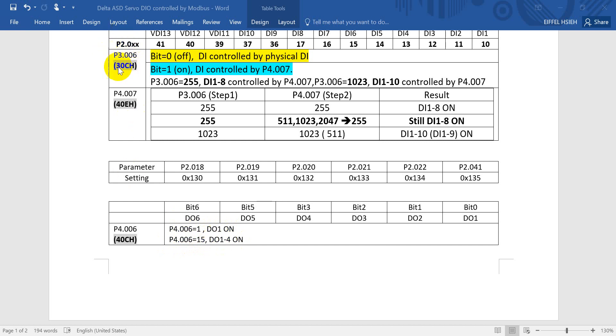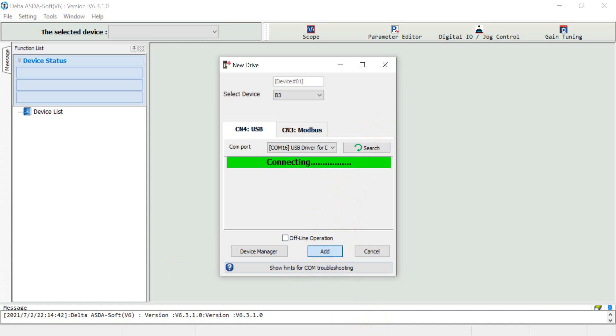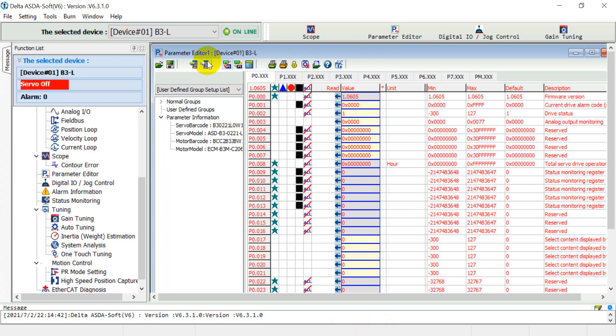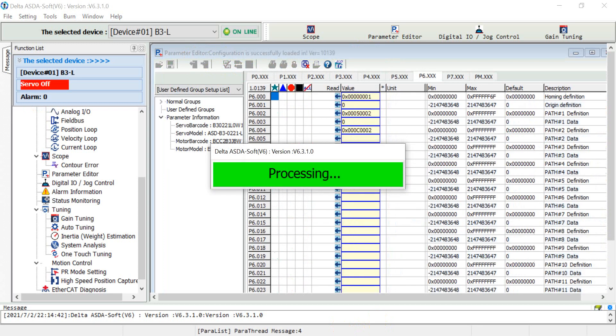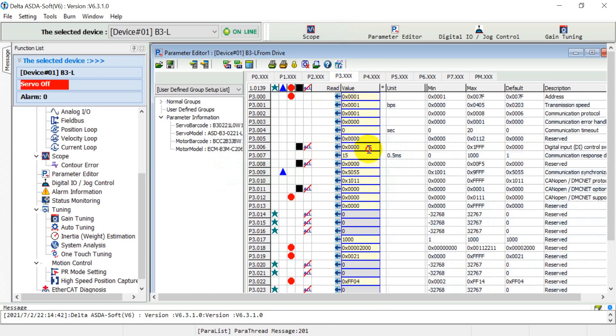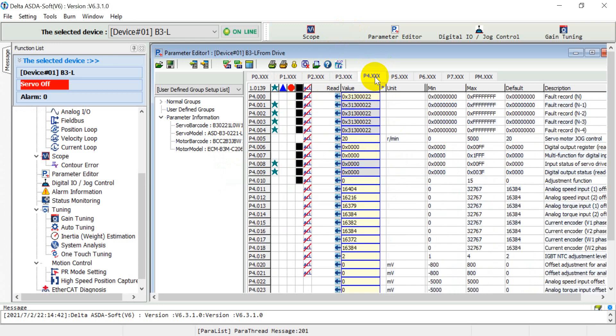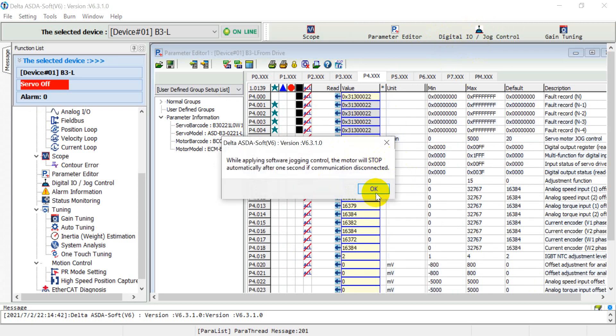Here you can see the gray background color indicates the Modbus address of these parameters. Now I will link to the servo drive so we can search and add the device. After that we can read the parameters back. So if you remember, here we have to give the value to P3-006 — we give 255 first. Then we can go to P4-007. Before that, we can open the digital input and output monitor to check the status.